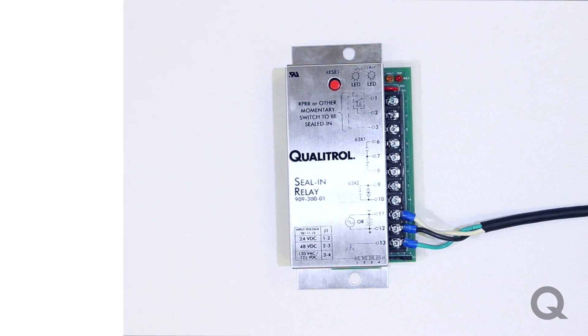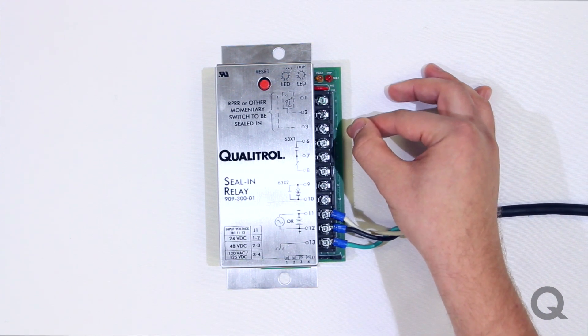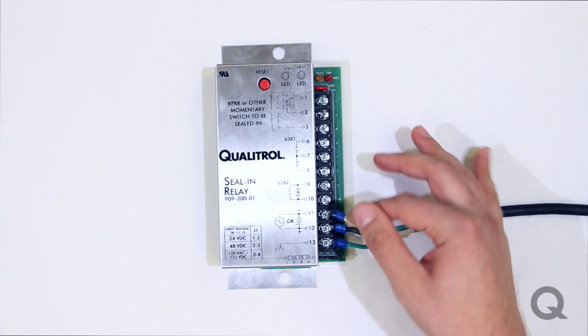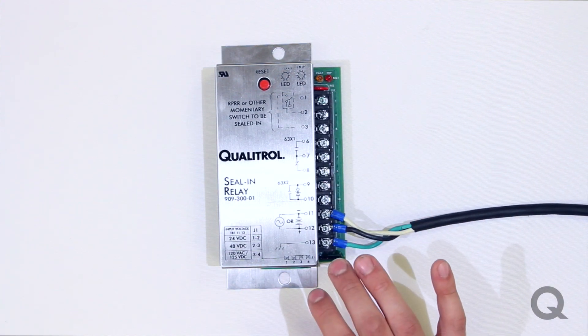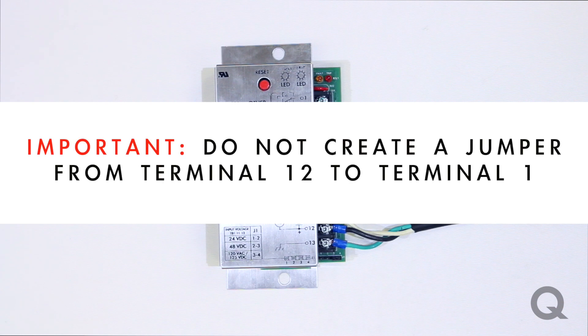On our new seal-in relays, we have the normally open at terminal 3. For our older models like the 909-200 series, we used to have our normally open at terminal 12. Do not create a jumper from terminal 12 to terminal 1 — the seal-in relay for the 909-300 would automatically do that internally. If you do create that jumper, it will cause a short and can cause damage to your board.